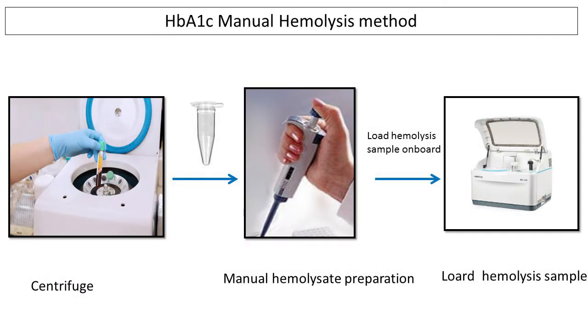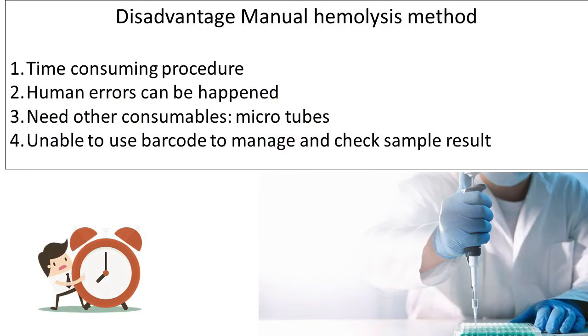For the manual hemolysis method, in biochemistry instruments that do not include the smart sampling method, we have to manually prepare the hemolysate by mixing lysis solution with red blood cells, allow some time to rupture all red blood cells and release hemoglobin, and finally load the prepared hemolysate to the analyzer as a sample to detect HbA1c results. Disadvantages include: it is a time-consuming procedure, human errors can occur, and additional consumables like microtubes are needed.